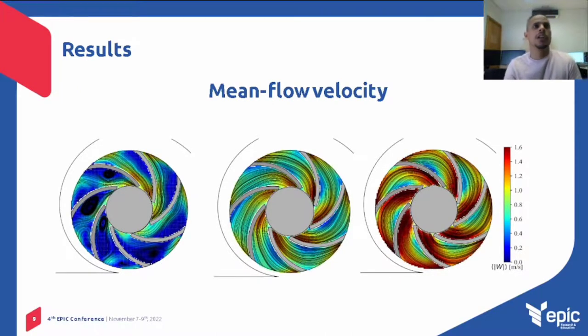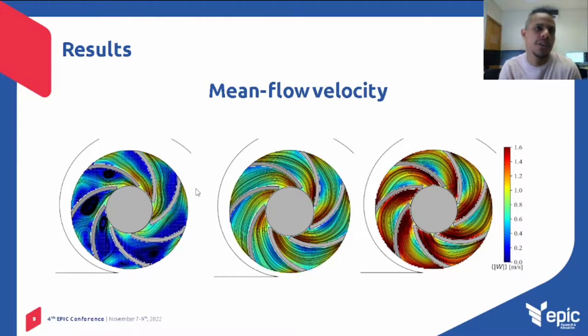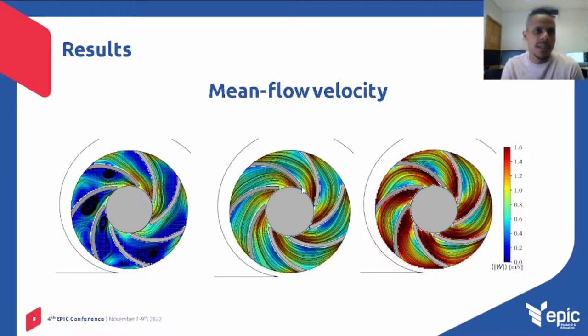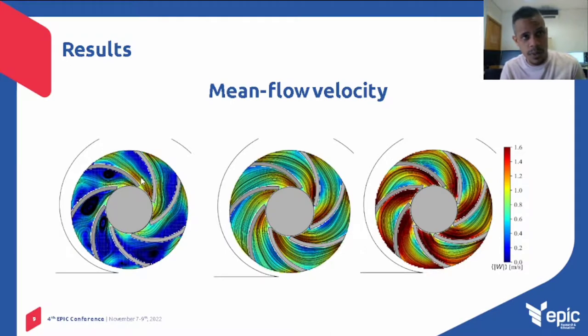Here I present some results of the work. The result of the average velocity field at the different flow rates is shown here for 0.3 BEP, 1 BEP, and 1.5 BEP. As can be seen in the design condition, the velocity vectors follow the geometry of the blades without significant flow separation. As the flow rate decreases to 0.3 BEP, the flow tends to have recirculation zones.